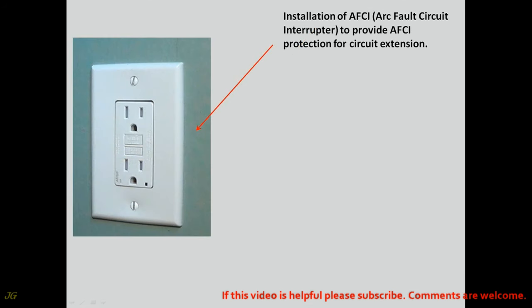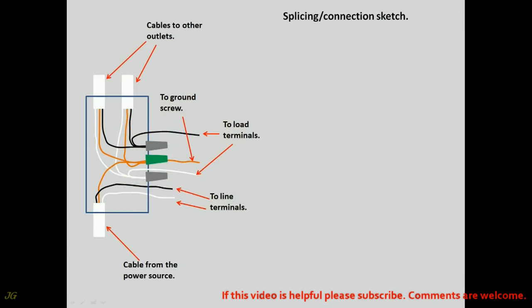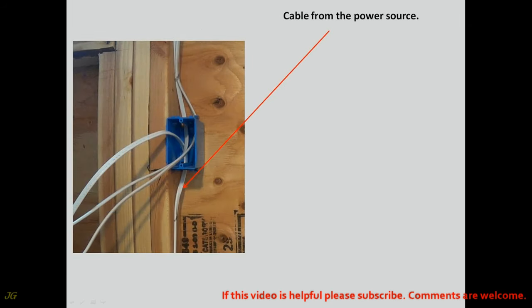Installation of AFCI, arc fault circuit interrupter, to provide AFCI protection for circuit extension. With the power cable left in the gutted room, install the AFCI receptacle in the outlet where the power cable enters. Splicing connection sketch. Cable from the power source.